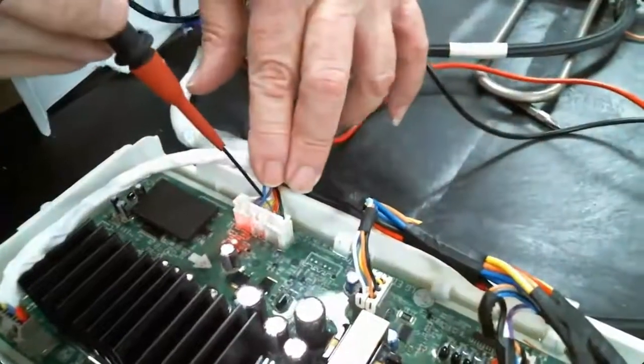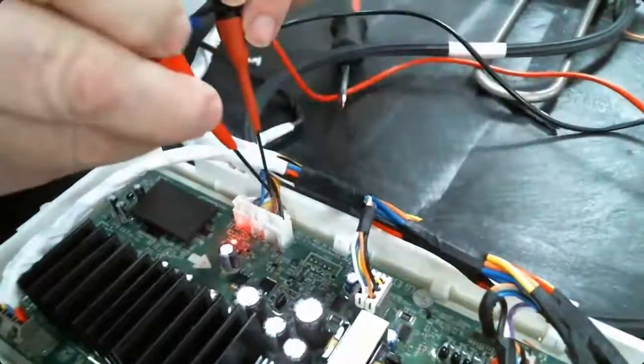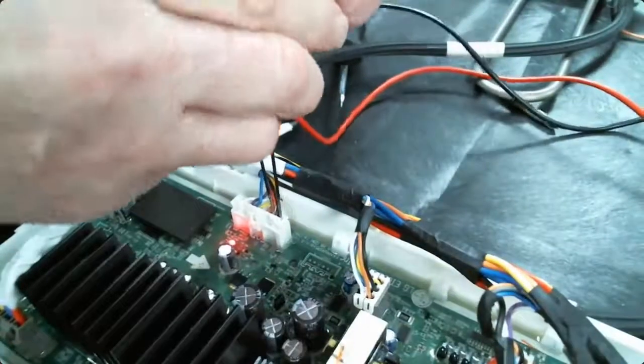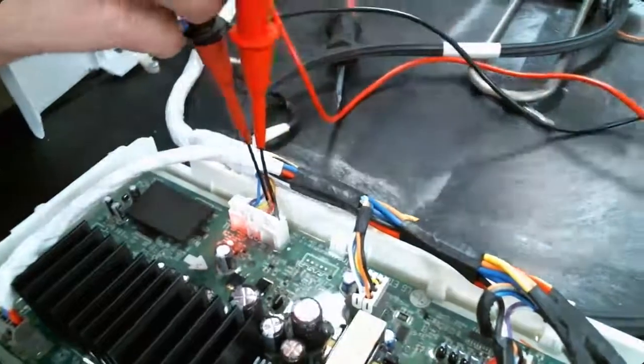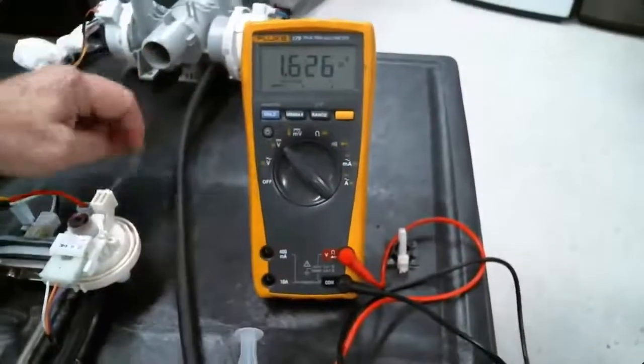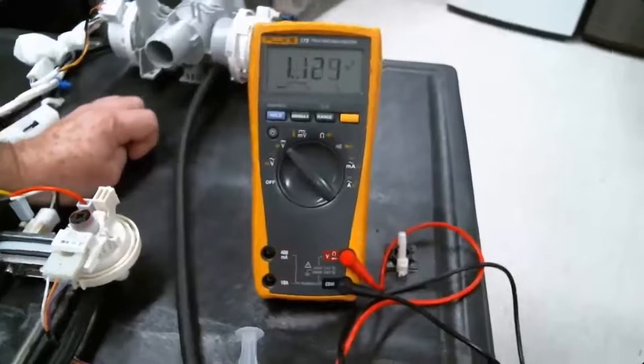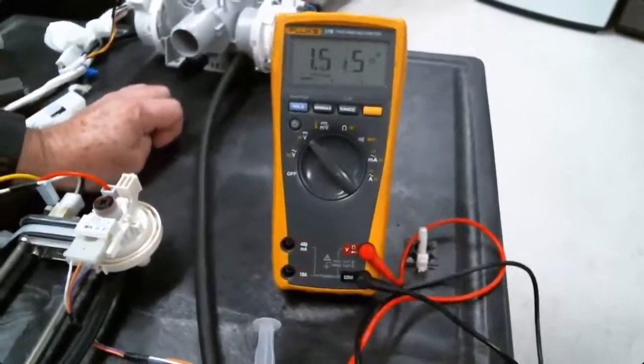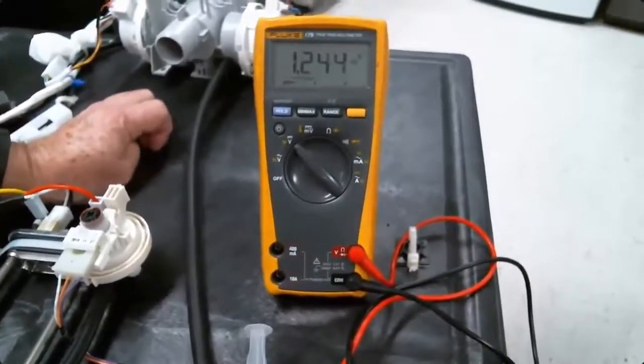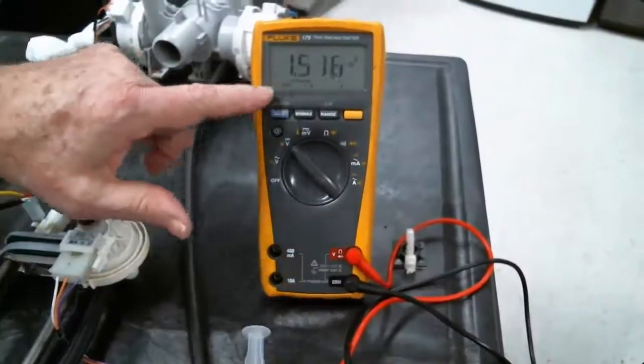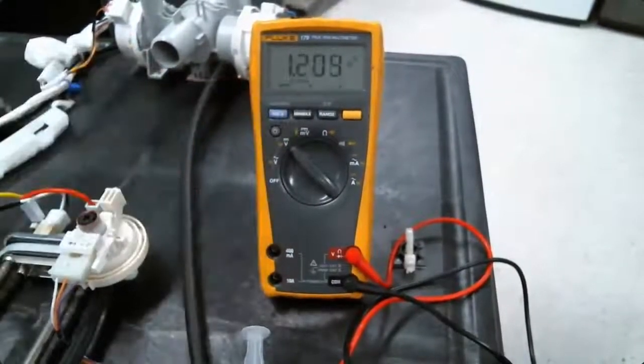The best way to check it is to put your meter leads across there - this should be pulsating voltage. You'll notice that hash mark at the bottom, and see how the voltage is bouncing around? That's really what you want to see - that's communicating. When it's steady, not pulsing, and you don't see those hash marks moving back and forth, you've got a problem.